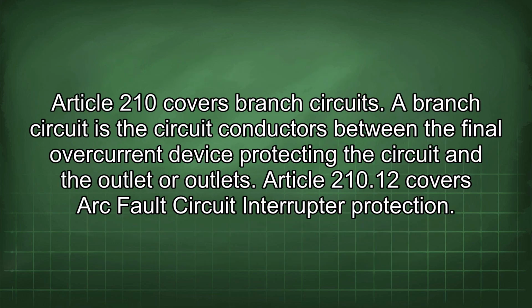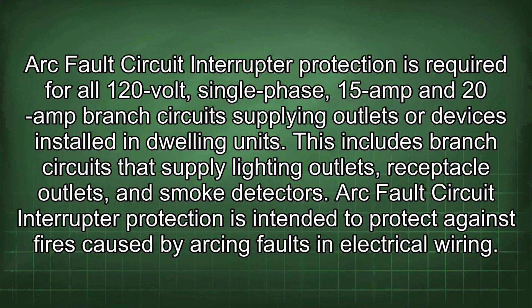Article 210 covers branch circuits. A branch circuit is the circuit conductors between the final overcurrent device protecting the circuit and the outlet or outlets. Article 210.12 covers arc fault circuit interrupter protection. Arc fault circuit interrupter protection is required for all 120-volt, single-phase, 15 amp and 20 amp branch circuits supplying outlets or devices installed in dwelling units. This includes branch circuits that supply lighting outlets, receptacle outlets, and smoke detectors.